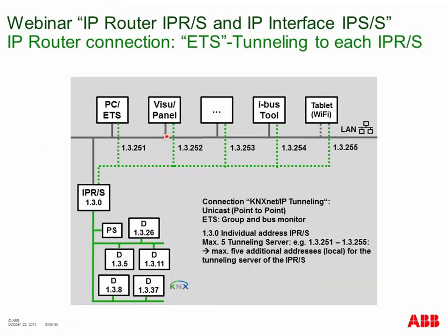Now the tunneling connection. Tunneling works the same as described for the IP interface. The IP router can simultaneously support routing and tunneling. For tunneling, we can connect, for example, ETS via PC, a visualization panel, the iBus tool, or a smartphone or tablet. Tunneling connections work as if the connected device is installed locally inside the line. One IP router can have a maximum of five tunneling connections at the same time. Each tunneling connection needs a physical address — for example the IP router itself has its coupler address such as 1.3.0, and each tunneling connection gets an additional address like 1.3.251 or 1.3.255.